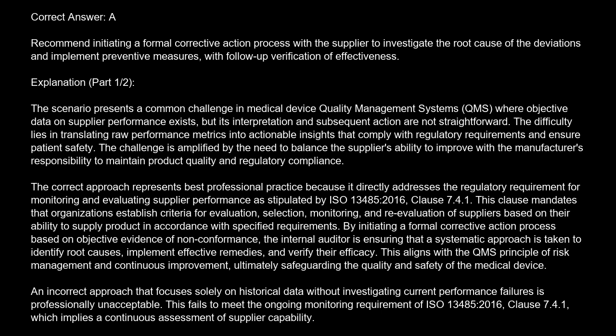The correct approach represents best professional practice because it directly addresses the regulatory requirement for monitoring and evaluating supplier performance as stipulated by ISO 13485-2016, Clause 7.4.1. This clause mandates that organizations establish criteria for evaluation, selection, monitoring, and re-evaluation of suppliers based on their ability to supply product in accordance with specified requirements.